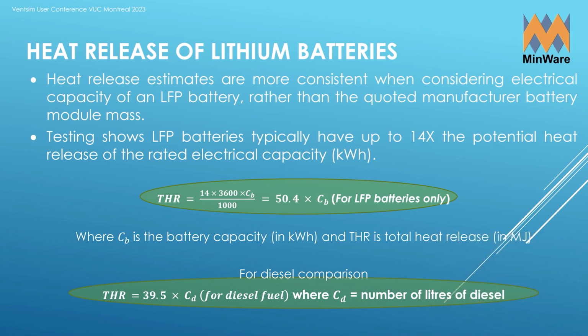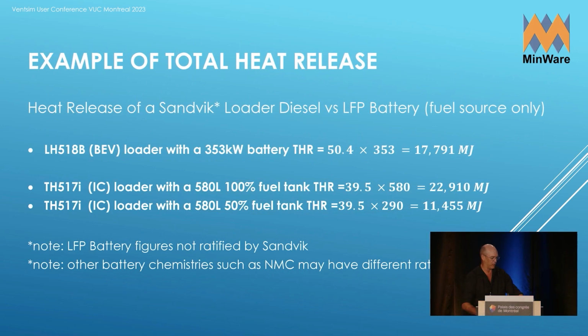Through looking at some test work, which I can supply later, there's enough experimental data to suggest that, at least for lithium iron phosphate batteries, there's a little calculation to work out how much heat load comes off the battery. For LFP batteries, you times it by about 50, times that by the kilowatt hour rating, and you get the thermal heat release rate of that battery.